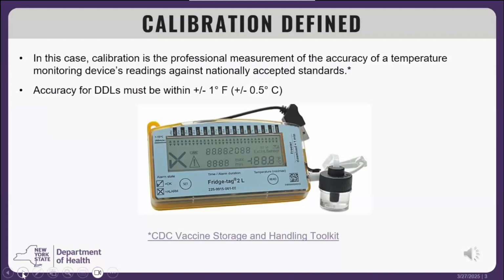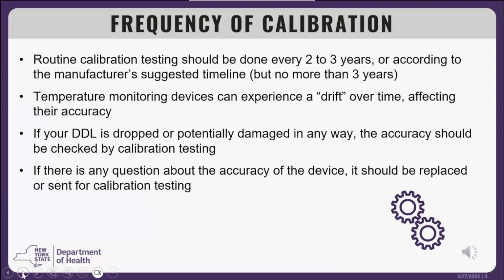Per the CDC's Storage and Handling Toolkit, linked here and on the resources document provided with this training, calibration is defined as the professional measurement of a temperature monitoring device's readings against nationally accepted standards. Accuracy for digital data loggers must be within plus or minus 1 degree Fahrenheit or plus or minus 0.5 degrees Celsius. Routine calibration testing should be done every 2 to 3 years, or according to the manufacturer's suggested timeline. The calibration certificate should indicate the date the device was calibrated and the date the next calibration is due. Data loggers must have calibration dates no more than 3 years from the date last calibrated.